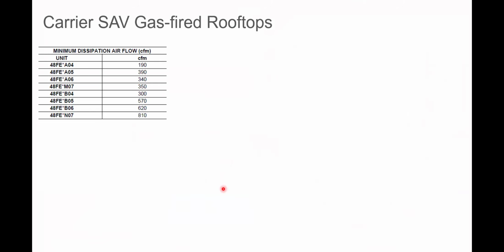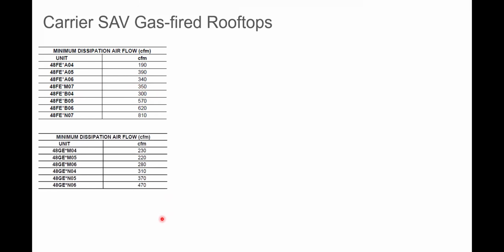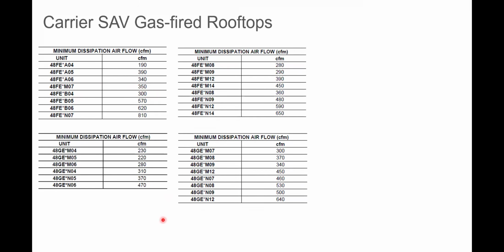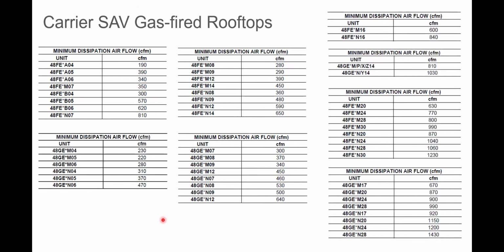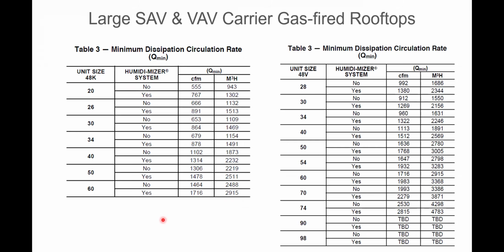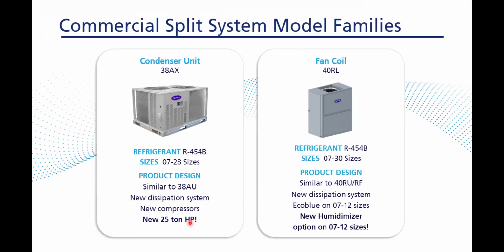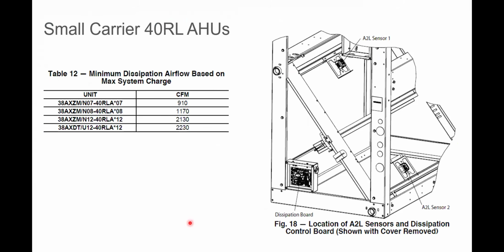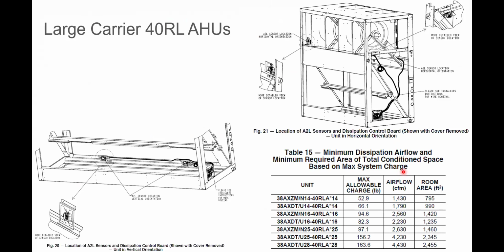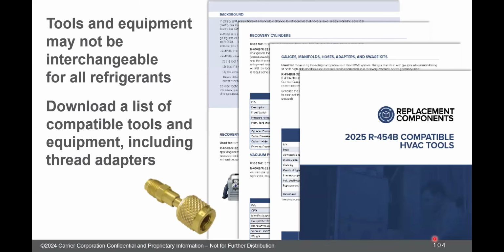Just like residential, on rooftop units or commercial air handlers, depending on how much refrigerant you have, or in the case of a rooftop, what model number you have, because that's how much refrigerant you have, there's a minimum CFM set up on the fan speed when you set the fan up to make sure that you have enough. The fan can go higher than that when you get a heating and cooling call, but the fan by itself needs to be at least that high. So that's published in every single manual. All I did was screenshot that out of every manual. And then we already showed you these ones and the bigger ones. So, air handler is commercially exact same thing. Nothing's different than anything I just said. There'll be a minimum CFM that you have to have. There'll be one or two sensors depending on the model of the unit. So no matter what it is, CFM, minimum square footage for the room, everything's exactly the same.